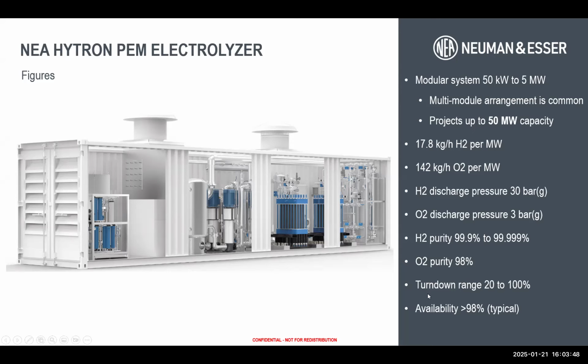You can have a pretty wide turn down range. The ramp up and ramp down of the system is very fast. That's typical of a PEM technology. And you can turn down the system all the way to 20%. And the availability and uptime is about 98%.